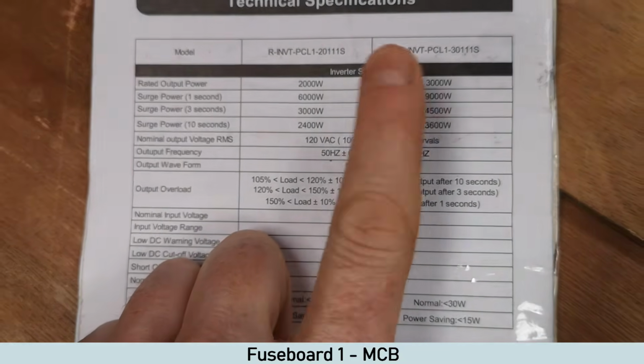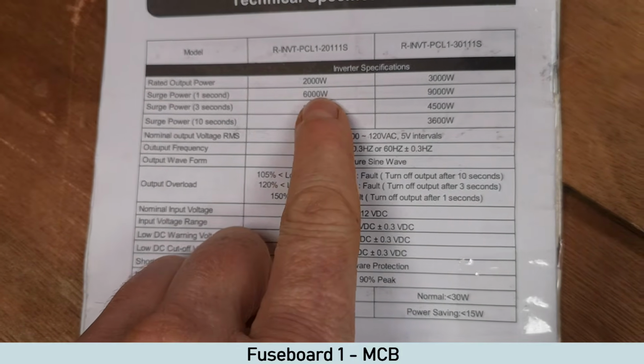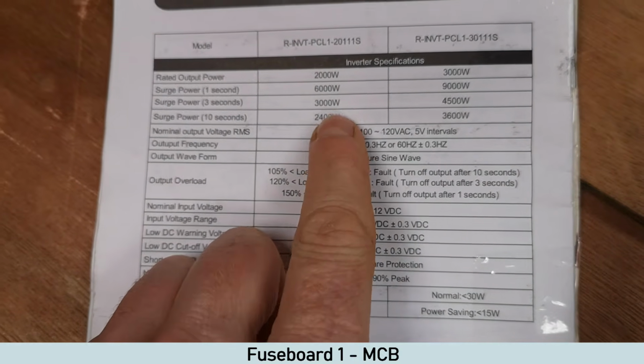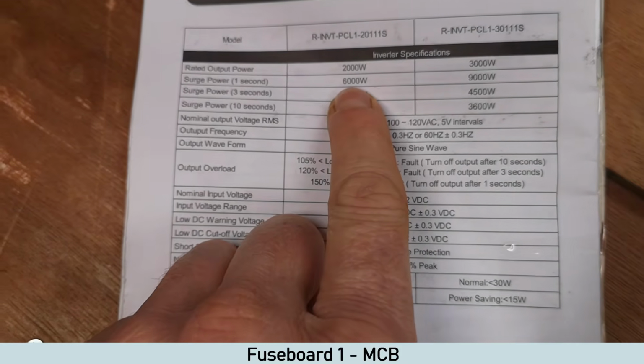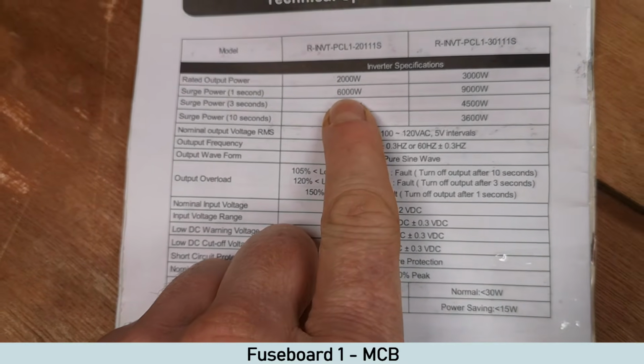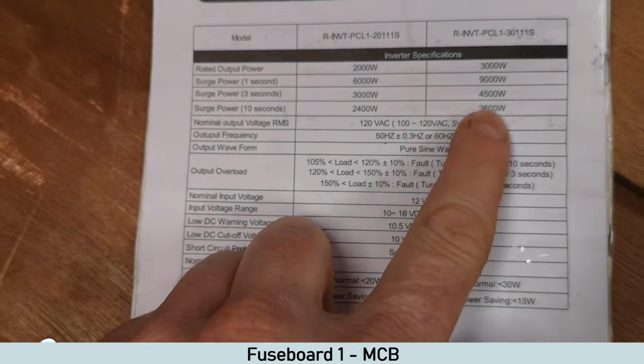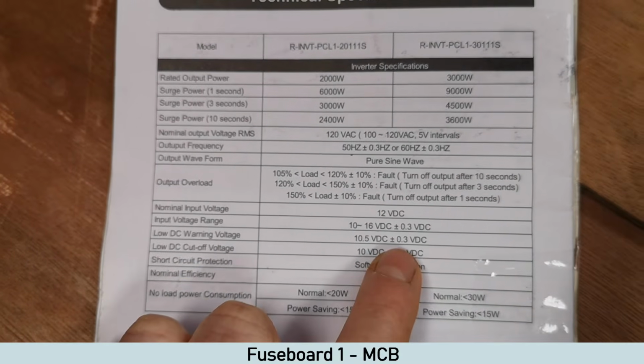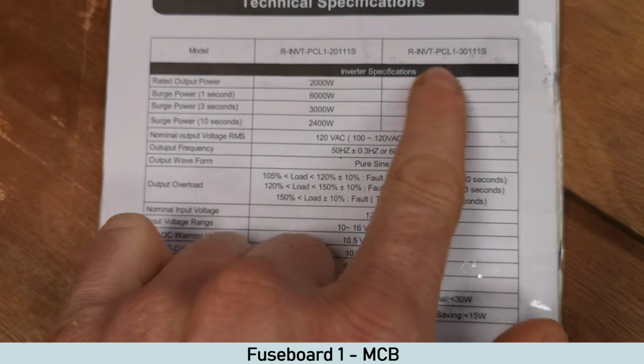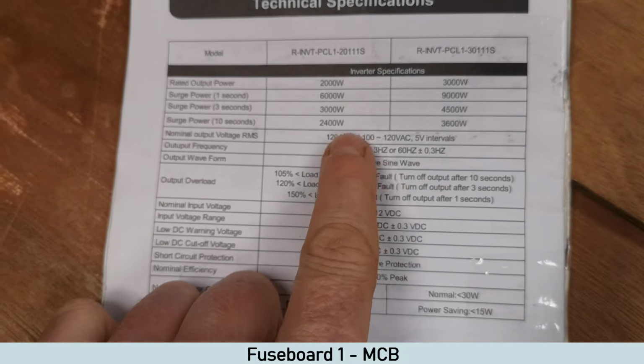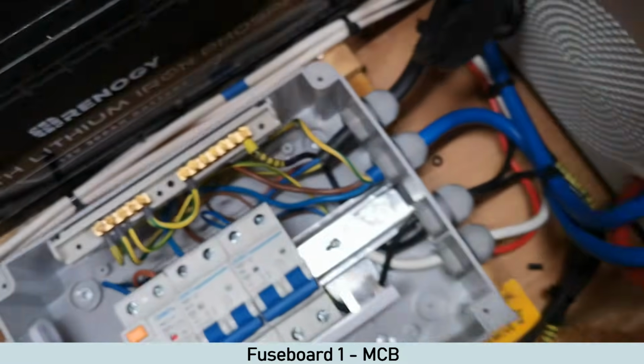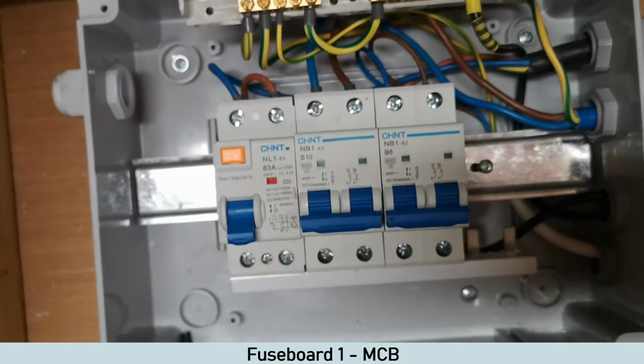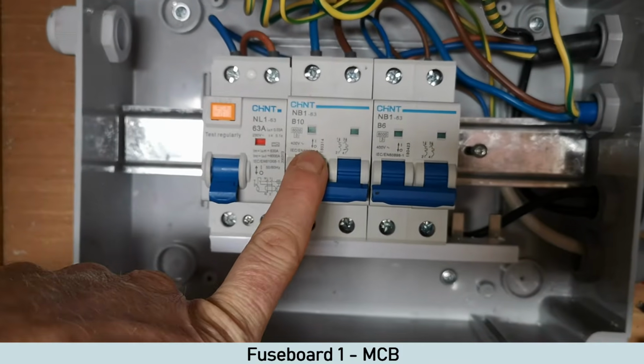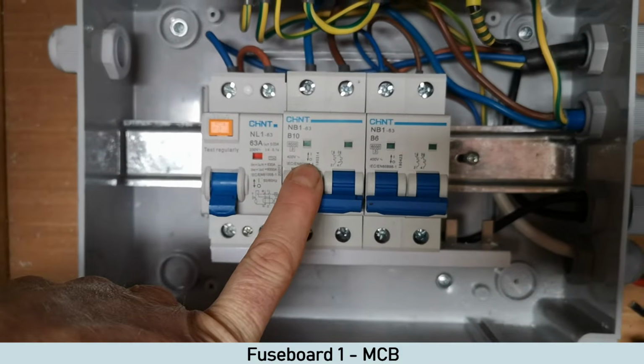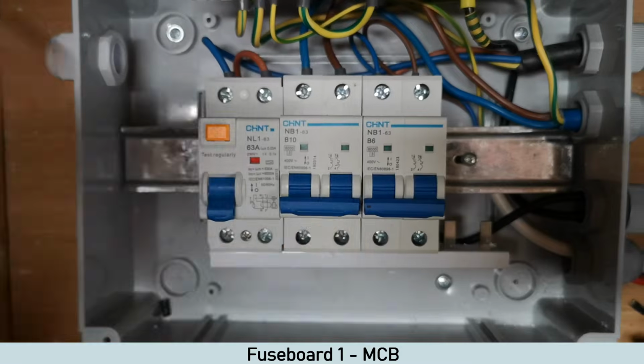Now obviously to do the maths with these, if you're in America and 120 volts, just divide the wattage by your voltage. So for example, 6000 watts divided by 120 gives you 50 amps. So you can see the difference it gives you. But obviously this all depends on the power you're going to be pulling through. And we've had our system installed for 2 years now with this breaker being in, and it's been fine. It's not tripped out, overloaded or anything, so all good.